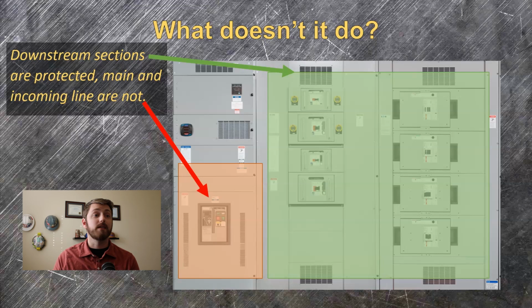The incoming cables and the bus on the line side, or incoming side of that main breaker, is only protected by the fuses on the primary side of the transformer outside that's feeding into it. This area doesn't trip for hardly anything, and enabling maintenance mode makes absolutely no difference if you're going to do work on the line side of that breaker.